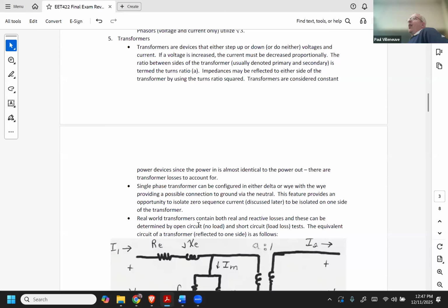Transformers are considered very efficient, to the point where you don't really have any power losses. So often when I do fault analysis or a calculation, I'll almost always neglect the value of resistance because it's so small. Transformers operating at full load are about 99% efficient, so that 1% loss is usually not enough to worry about, unless you're trying to sell joules and need to track every bit of loss.